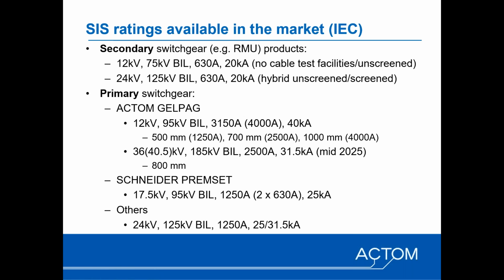The I²R losses are something which is always a challenge with solid dielectric switchgear, and Johan will touch on that in his portion of the presentation. But what's remarkable is that it's 40 kiloamp short circuit rated, and the width of the panel up to 1250 amps would be 500 millimeters, 700 millimeters up to 2,500 amps, and then for the 4,000 or 3,150 it would be 1 meter wide, which is a considerable space saving compared to other alternatives.